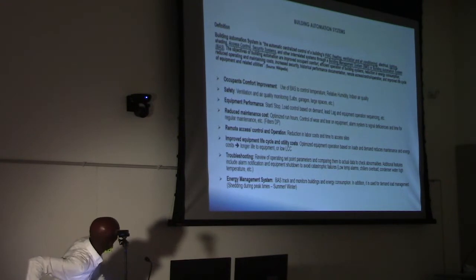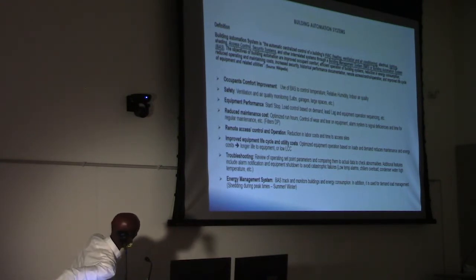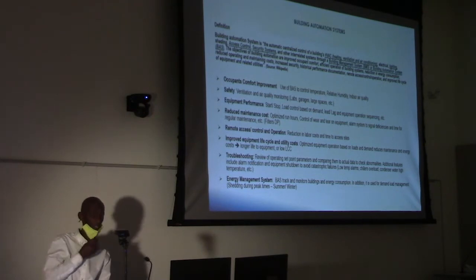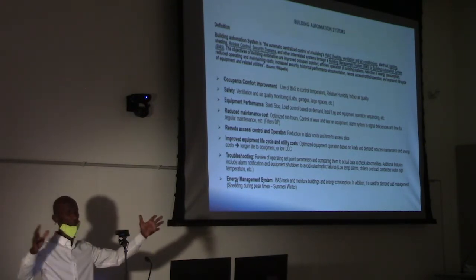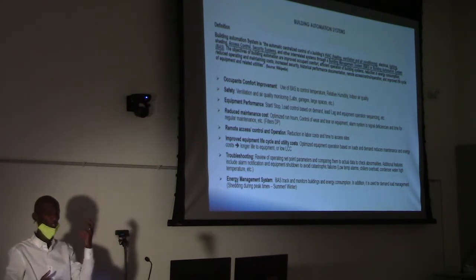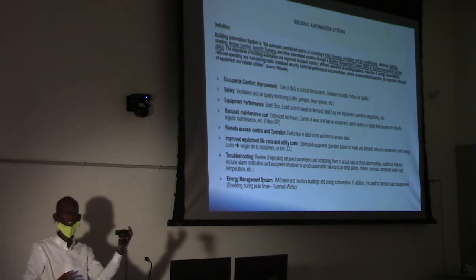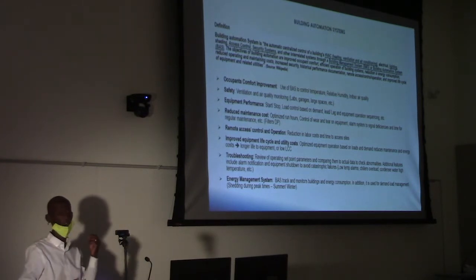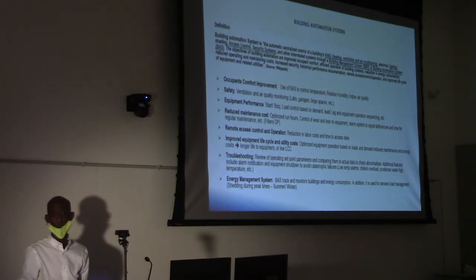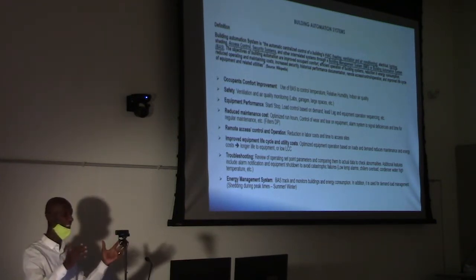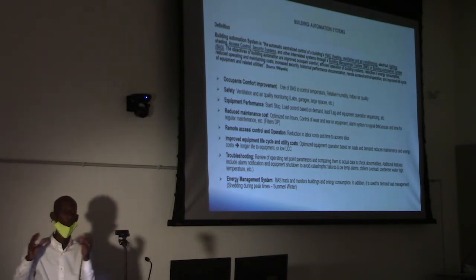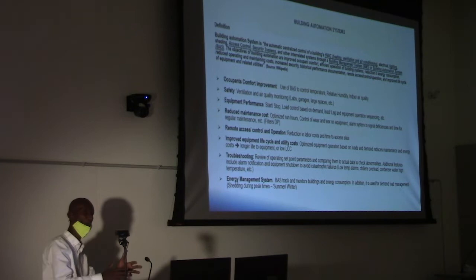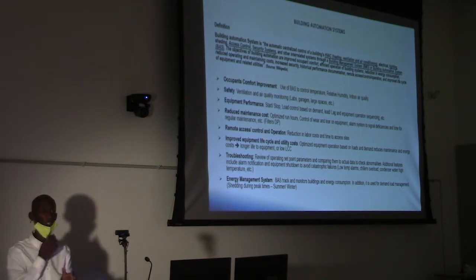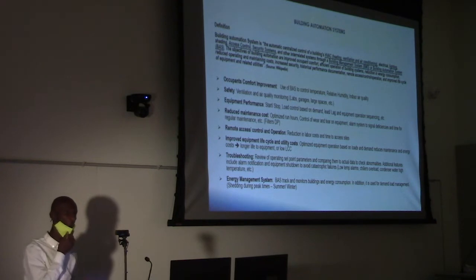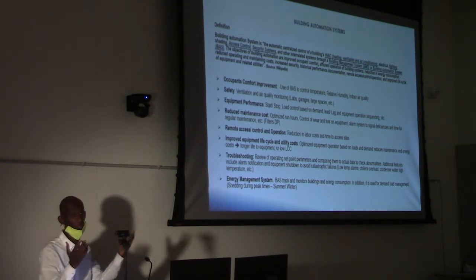The other thing is lead lag and equipment operating systems, so sequencing. What happens is, just an example, if you have 3 pumps, if you have 1 pump running all the time, guess what, the other 2 are not running. After a certain period, that pump is going to burn out, and then you have to start the other one. What we do is alternate them so that they don't wear. You don't put pressure on one and don't wear the other one. So we alternate them so that they have equal time of operation. Those are a few things the system does.